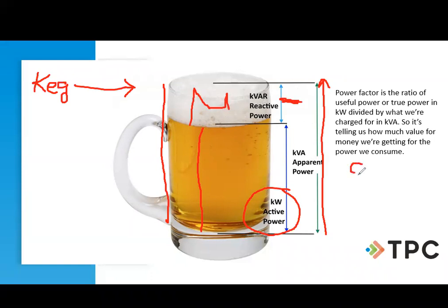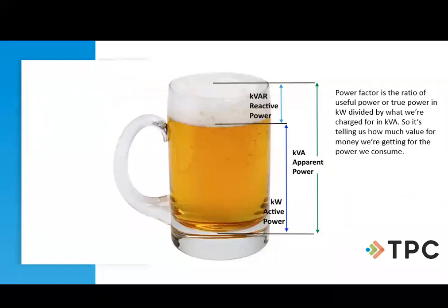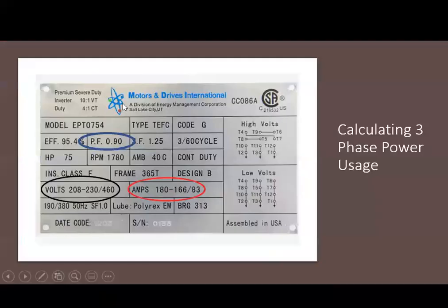So no matter what our source is, it has to produce enough power so that we can charge our capacitors, energize our coils, and make motors turn. But some of that is going to be just surging back and forth in the line, not something that actually is utilizing the power for actual work. So that's how I kind of like to explain that one a little bit. We'll do a three-phase calculation so you can actually see it. This is going to be for a motor.